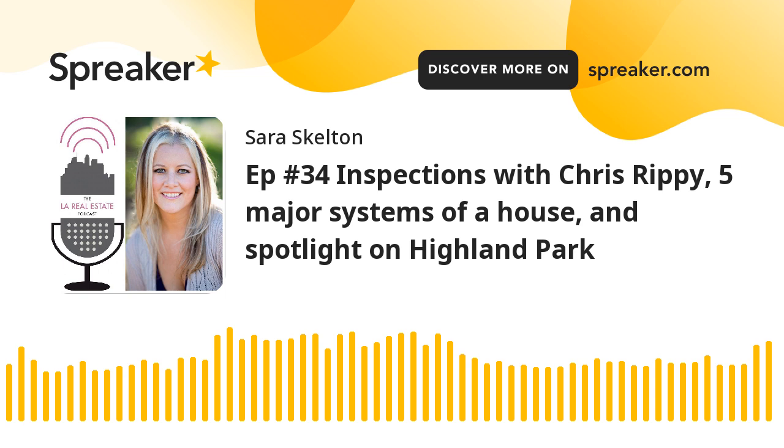That's correct. Pretty nice. And then, Chris, what about electrical, like addressing electrical? So we have some of these very old homes with old panels. What do you look for when you see these old panels as far as it being safe or any things that you notice? And the one thing I do see in a lot of inspections is double tapping of the wires. I've seen that over and over and over the years.